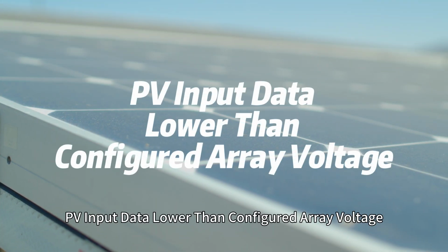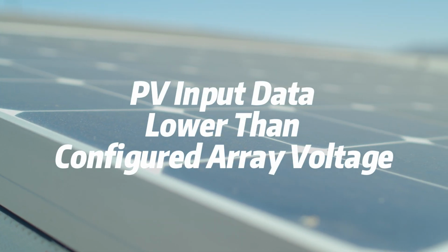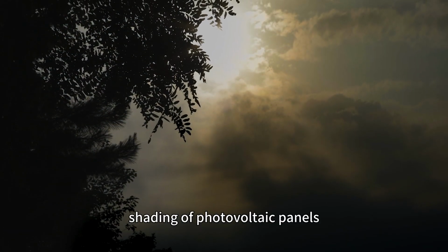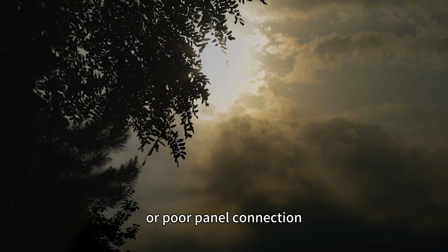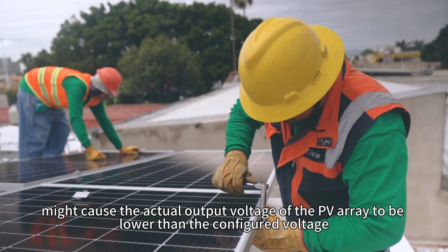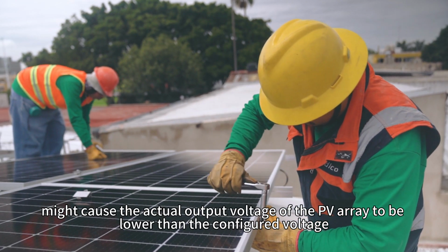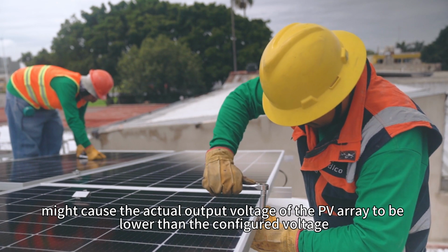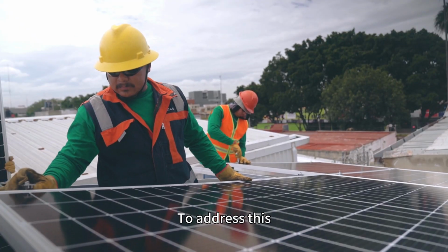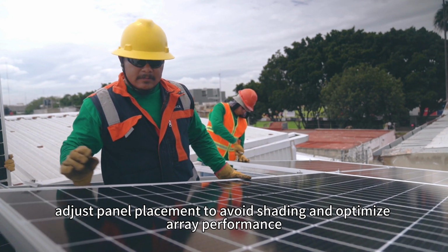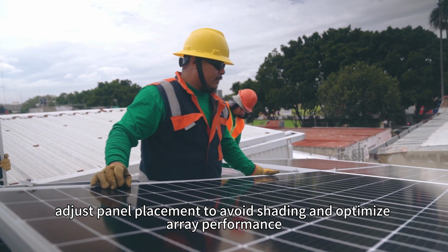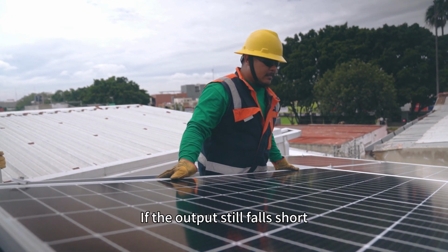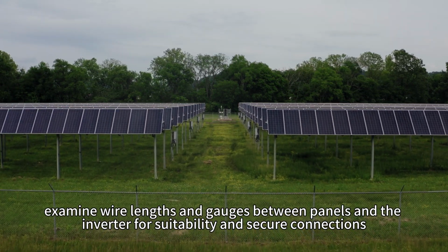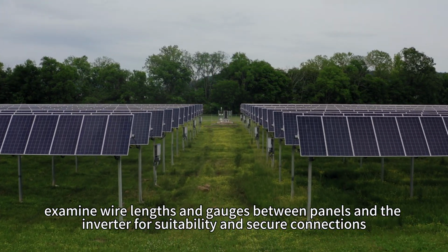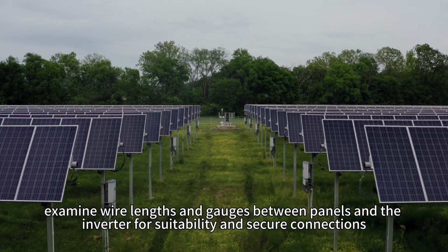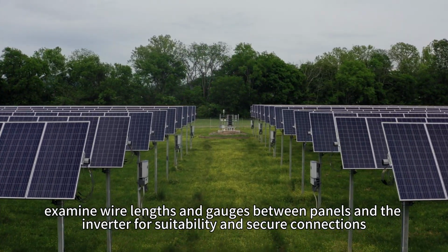PV input data lower than configured array voltage. Cloudy days, shading of photovoltaic panels, or poor panel connection might cause the actual output voltage of the PV array to be lower than the configured voltage. To address this, adjust the panel placement to avoid shading and optimize array performance. If the output still falls short, examine wire lengths and gauges between the panels and inverter for suitability and secure connections.